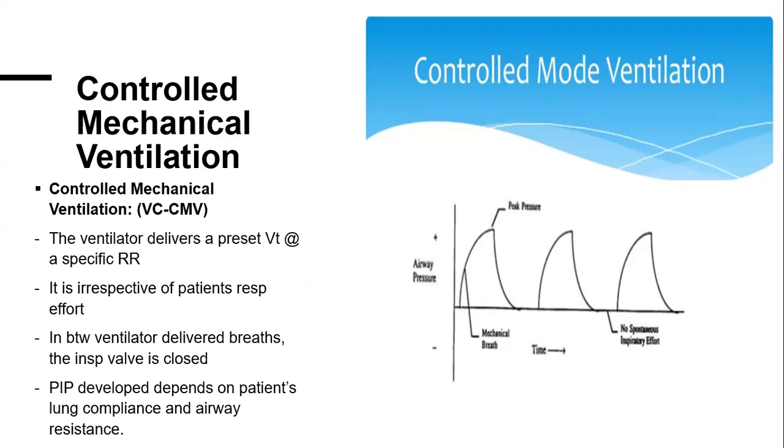If you can see it here, all these are mechanical breaths. These are ventilator breaths. These are ventilator breaths. In between these ventilator breaths, there is no spontaneous effort from the patient. In between ventilator-delivered breaths, the inspiratory valve is closed, so this patient is not allowed to take any inspiratory effort.